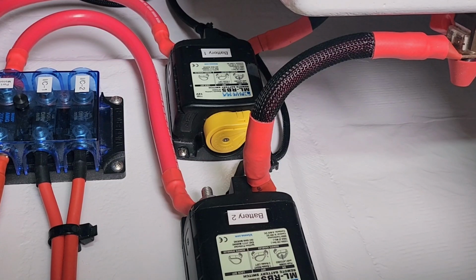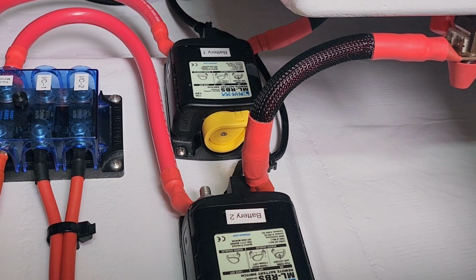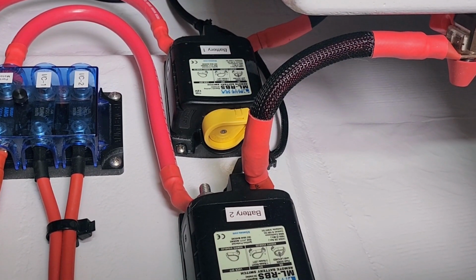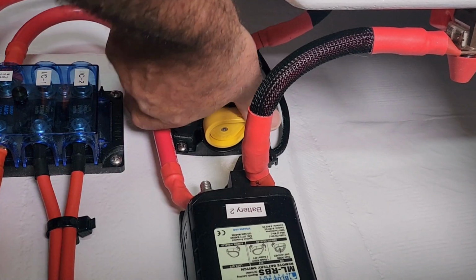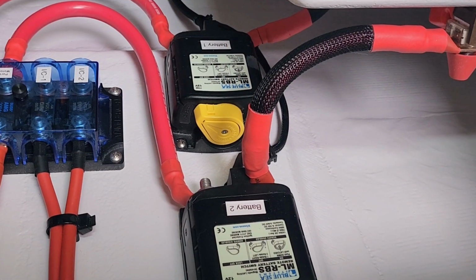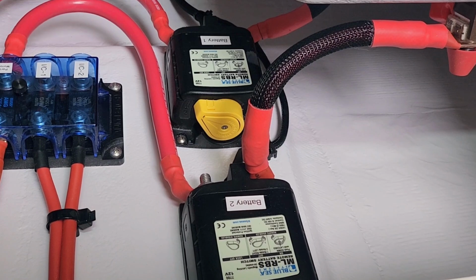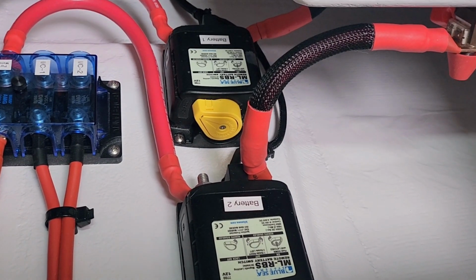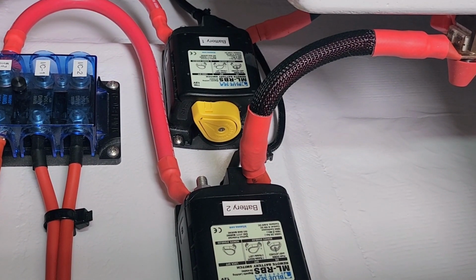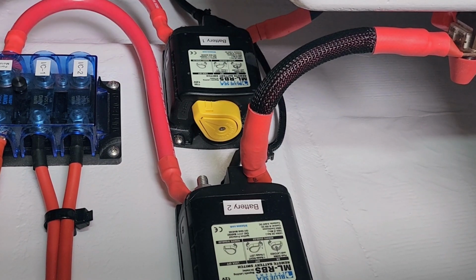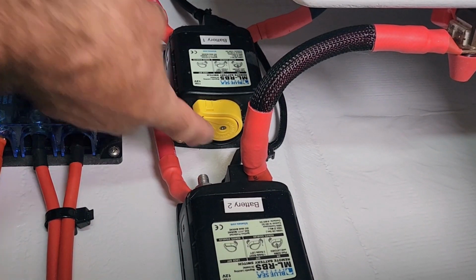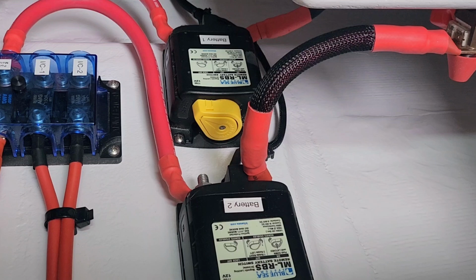Why did the batteries fault? And if I think the condition is cleared and it's safe to turn the batteries back on, I can manually turn the batteries back on. What's nice about this is that I can also manually turn the batteries off. Now they're locked out. I can do maintenance, and there's no way that someone from another panel somewhere could turn the batteries on, or that they could accidentally be reconnected. There's just no way to turn it back on.